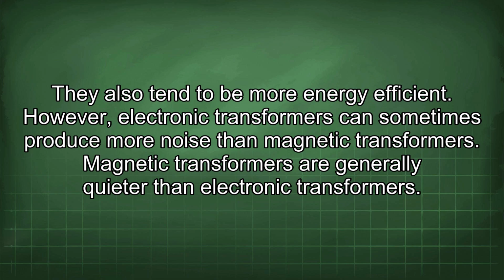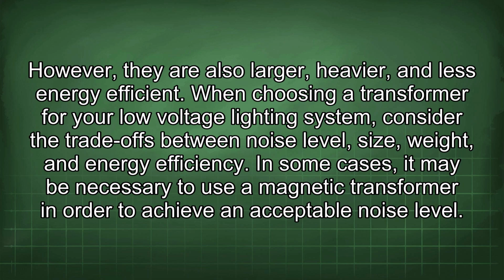Magnetic transformers are generally quieter than electronic transformers. However, they are also larger, heavier, and less energy efficient. When choosing a transformer for your low-voltage lighting system, consider the trade-offs between noise level, size, weight, and energy efficiency. In some cases, it may be necessary to use a magnetic transformer in order to achieve an acceptable noise level.